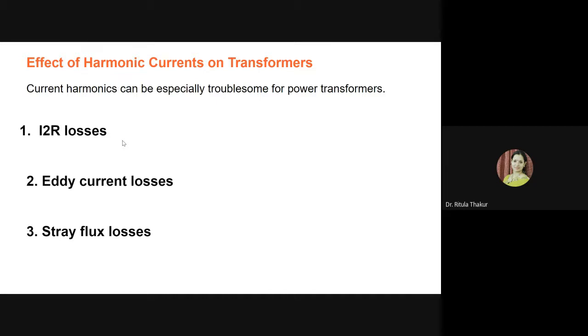If the RMS value of the load current is increased due to the harmonics, and we know that harmonics are nothing but multiples of the fundamental frequency, then when the current increases due to the harmonic component, you can well imagine the I square. What will be the impact of that increase in the current? Accordingly, all these losses will be compounded. So how will it affect the power transformer? The power transformer will consume more real power than anticipated, making the efficiency of conveying power to the consumers lower.